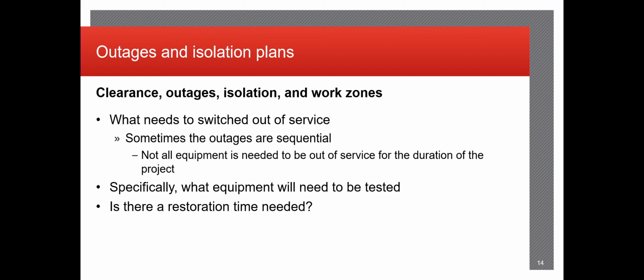So what they usually plan for when they initially design the substation is to allow multiple instances where you can open up maybe 2 or 3 or maybe even more breakers to isolate a specific portion of the substation without killing it altogether, allowing transmission lines and distribution lines to still feed and receive power. In our case, when we are asked to upgrade or test any equipment that is currently in service and will be put out of service temporarily, we need to identify that before we even show up on site. What necessary equipment needs to be operated, needs to be taken out without affecting anything that surrounds it.